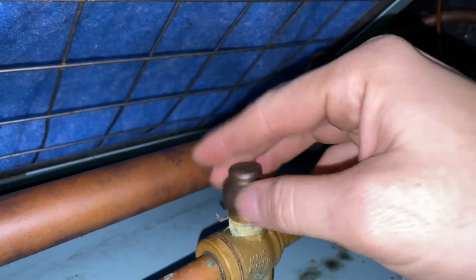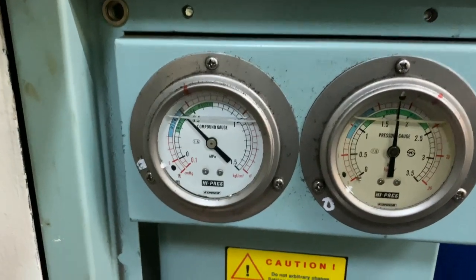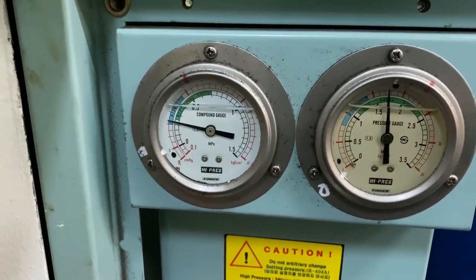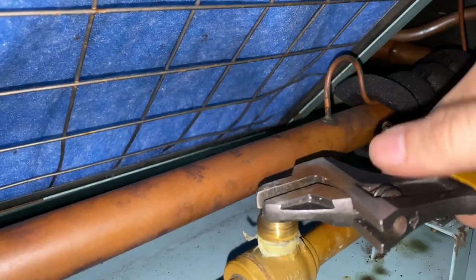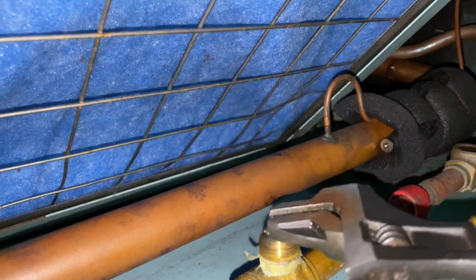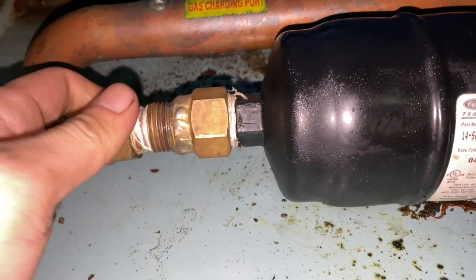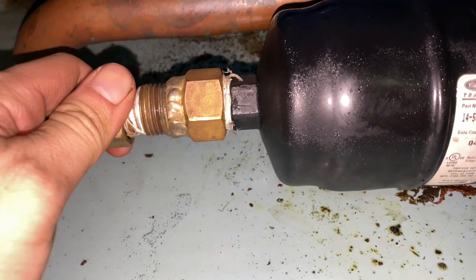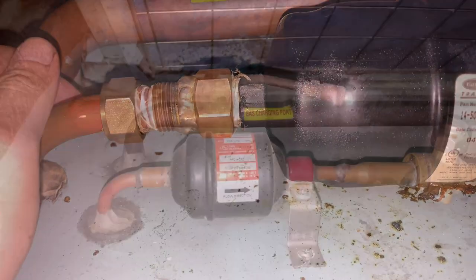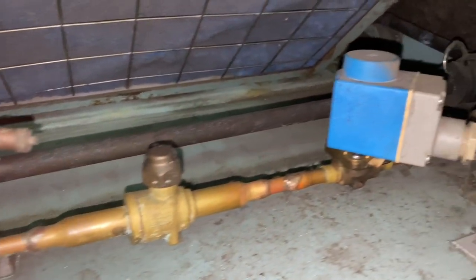You need to close the liquid line service valve after the condenser, then run the unit until the suction becomes completely vacuum. Then close the shut-off valve after the filter dryer. Since the filter dryer is blocked, make sure to crack open the screw first because there is still pressure on the line. Good thing this package aircon was already modified, so we don't need to do the brazing.